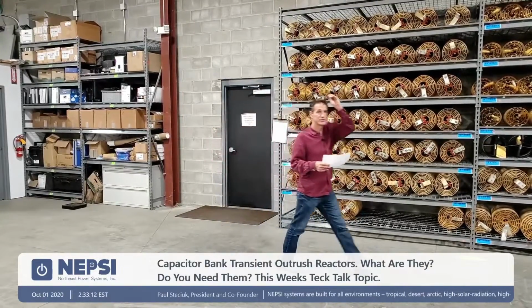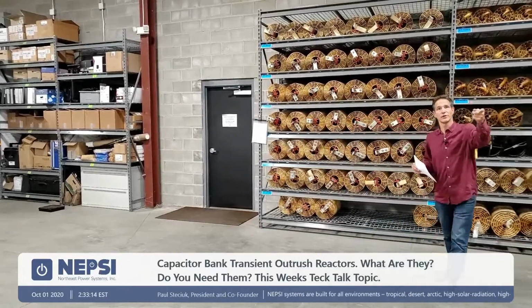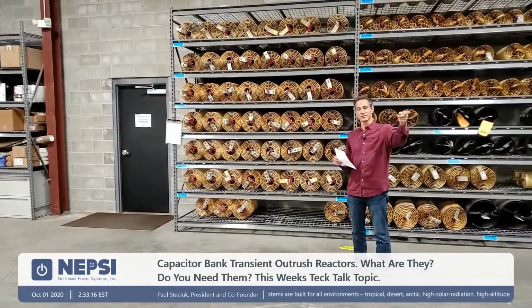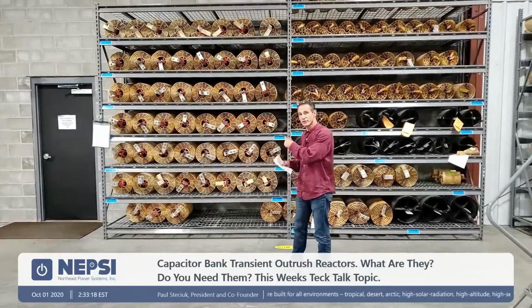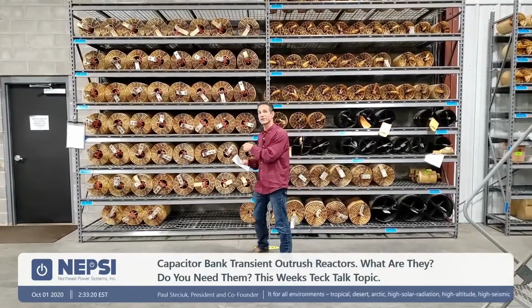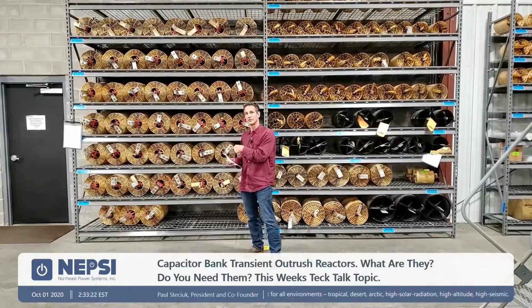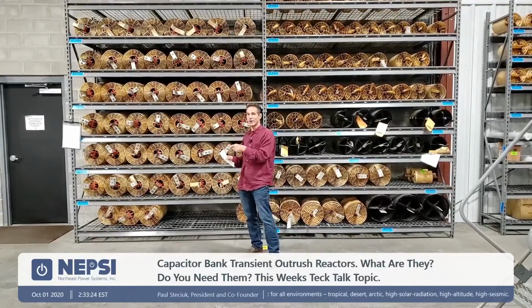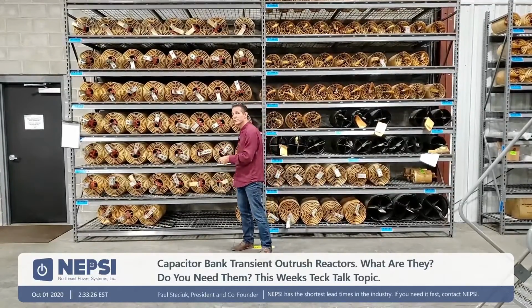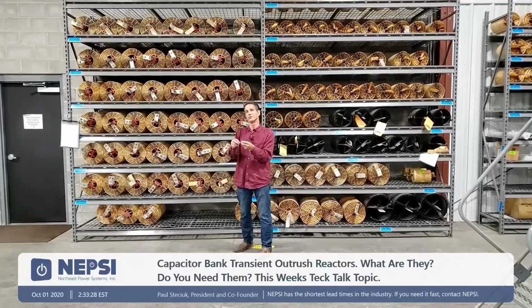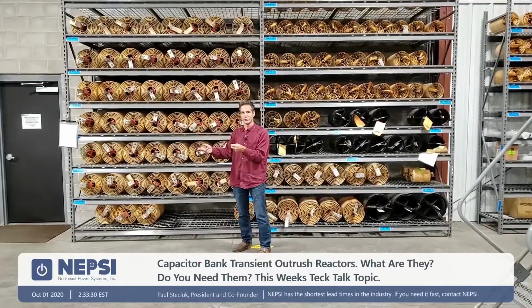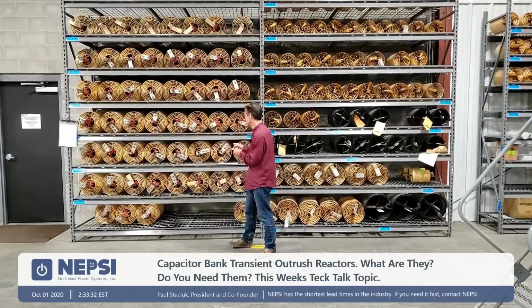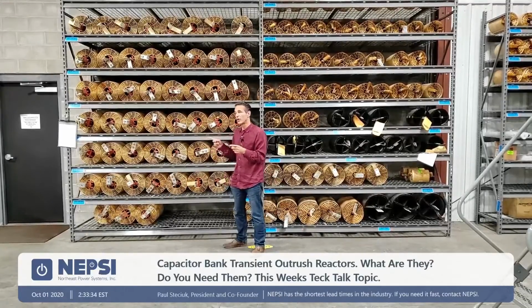All right, in the shop. So before we get going on this capacitor bank, let's talk about transient inrush reactors. We had a tech talk a while back about transient inrush reactors. Transient inrush reactors can help support the required inductance to reduce the amount of outrush current you get from your capacitor bank. But transient inrush reactors are typically smaller.